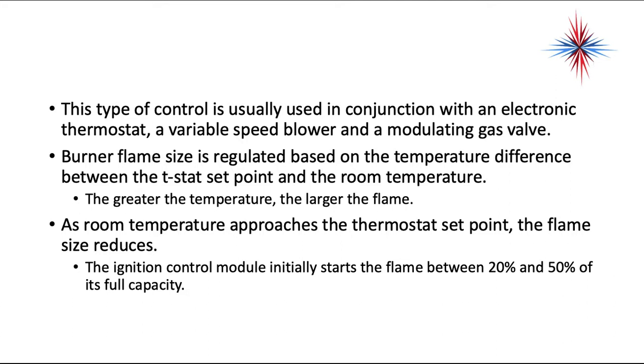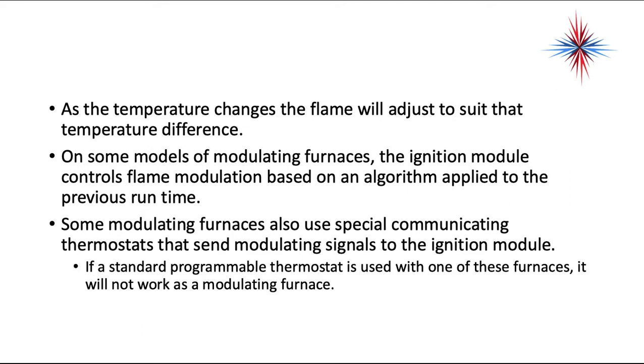The greater the temperature difference, the larger the flame. As room temperature approaches the thermostat set point, the flame size reduces. The ignition control module initially starts the flame between 20 and 50% of its full capacity. As the temperature changes, the flame will adjust to suit the temperature difference. On some models of modulating furnaces, the ignition module controls the flame modulation based on an algorithm applied to the previous runtime. Some modulating furnaces also use special communicating thermostats that send modulated signals to the ignition module. If a standard programmable thermostat is used with one of these furnaces, it will not work as a modulating furnace.